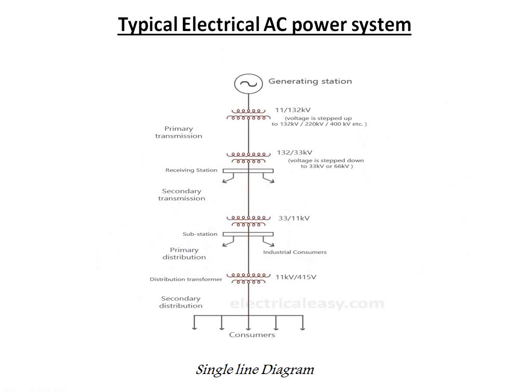This is a single line diagram of a typical electrical AC power system. We can see that the generating station generates voltage in the range of 11 kV, and then it is stepped up by using a step-up transformer rated 11 kV to 132 kV. The voltage is stepped up to 132 kV, 220 kV, or 400 kV depending on the system.